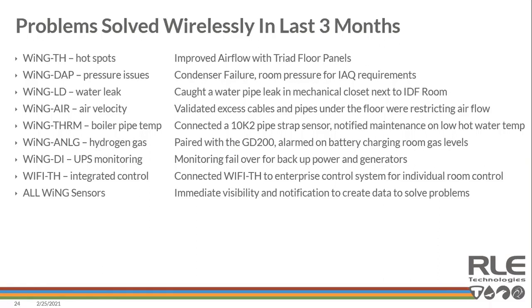We were also talking with another one of my partners - they had gas in the battery charging room at increased levels. So we integrated our analog transmitter and used the 4 to 20 milliamp output on that hydrogen gas sensor to create that alarming strategy.